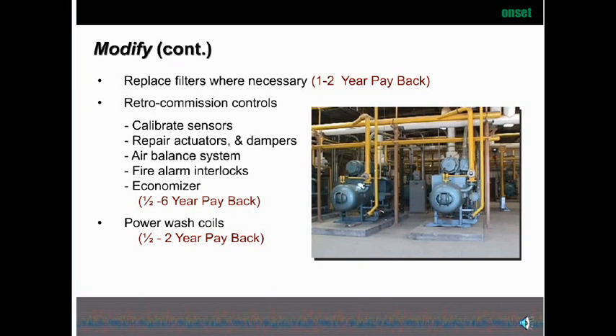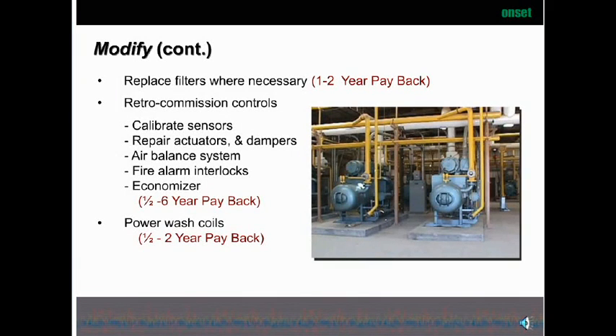Retro-commission your controls — that means calibrating your sensors, repairing actuators and dampers, and balancing your system. Regarding fire alarm interlocks: we've found many systems where the fire alarms are not interlocked to the system, which is not to code. Also consider your economizer — if you don't have one, think about putting one in, and if you do have one, make sure it's functioning properly. We truly recommend always power washing your coils because that cleans them up and makes them very efficient for thermal transfer.